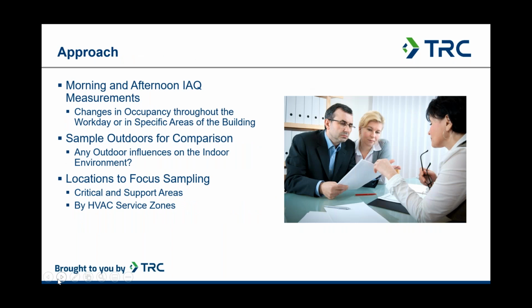So some suggested approaches on indoor air quality monitoring include conducting morning and afternoon measurements to try to reflect changes in occupancy throughout the workday or in specific areas of the building. Sometimes we see carbon dioxide levels rise later in the day as the building becomes more occupied. Now, later in the presentation, Dave will be discussing some sensor technologies where you can actually do continuous monitoring for these indoor air quality parameters.